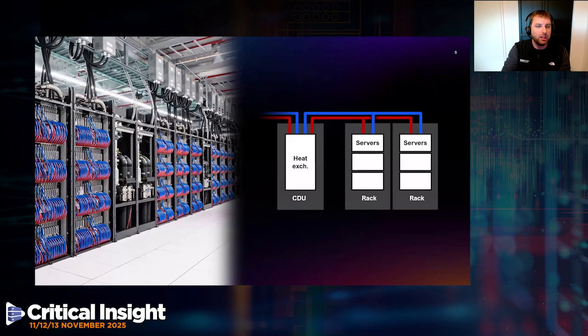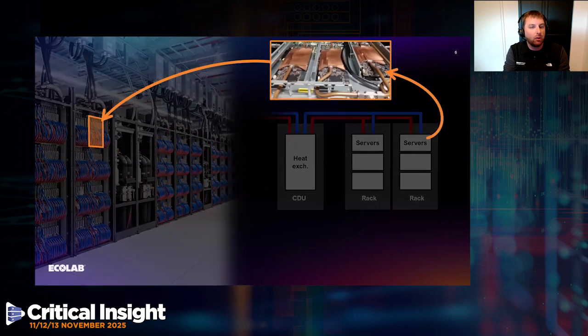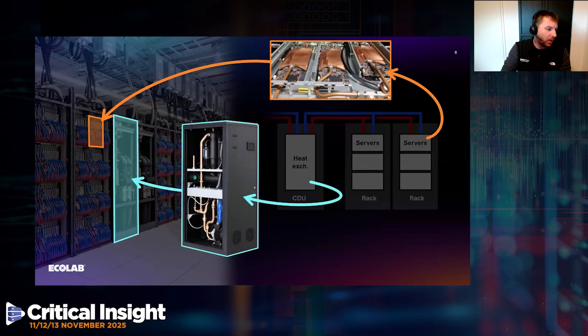To be a bit more graphic, in the white space on the data floor we have these servers or nodes exchanging heat through copper or aluminum cold plates to a so-called cooling distribution unit, which is often on the same data floor. This unit exchanges heat from the secondary direct-to-chip loop to the primary loop to get the heat out of the room.